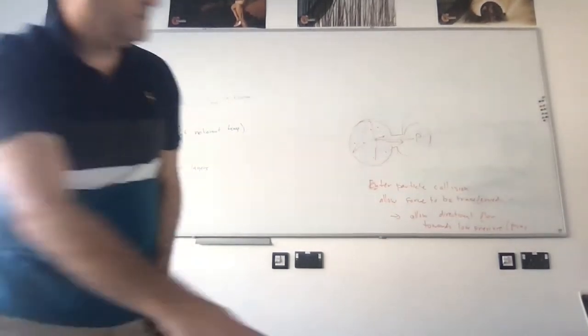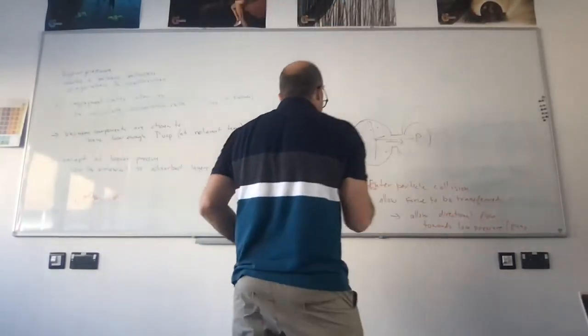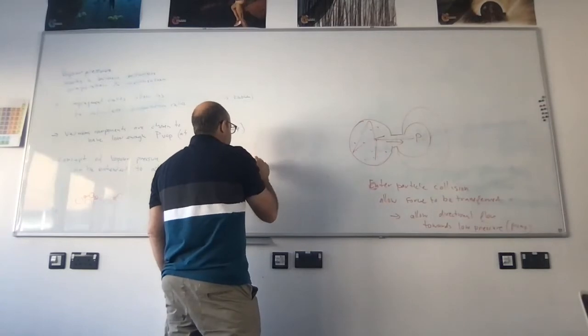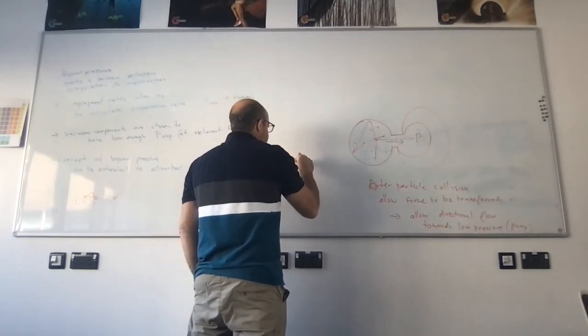It would basically extract gas and push it into a high pressure. So all these pumps, if you operate them in one direction, are compressors. You'd use them to fill air in your tire, whatever. If you reverse them, they become pumps. Later, have a look at this thing. The idea is that you could use a principle called positive displacement. These are positive displacement pumps.